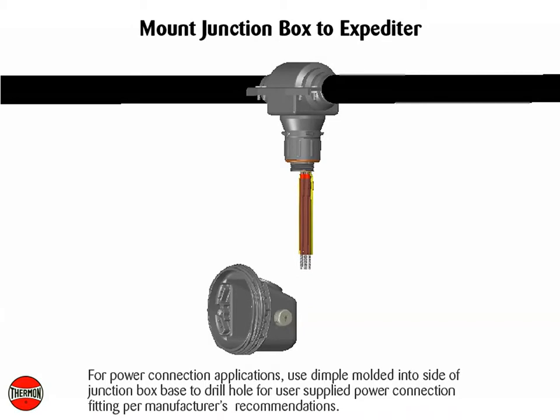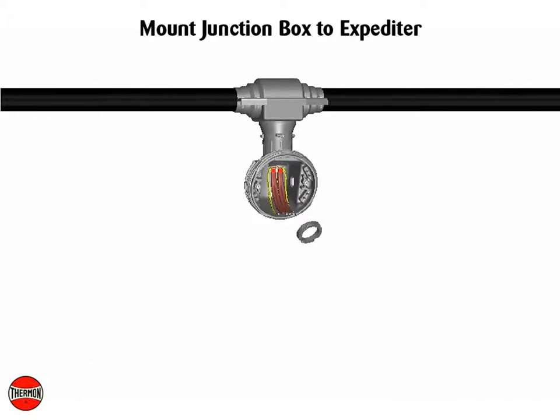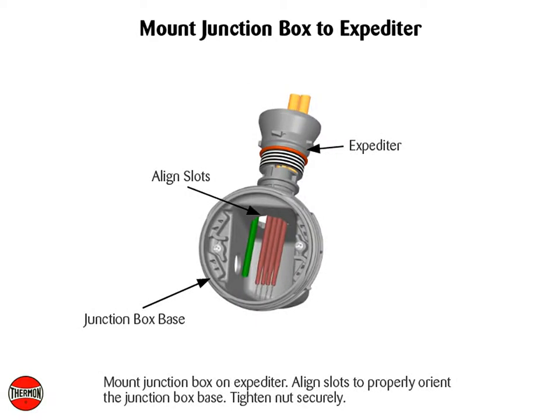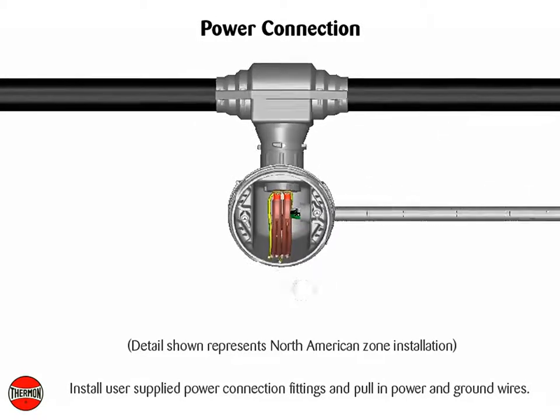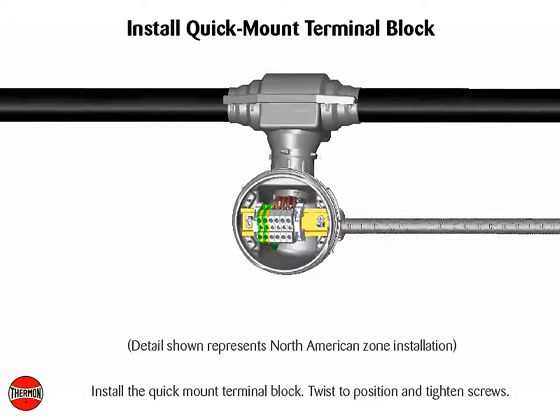For power connection applications, use the dimple molded into the side of the junction box base to drill a hole for the user-supplied power connection fitting, per manufacturer's recommendations. Mount junction box on expediter. Align slots to properly orient the junction box base and tighten nuts securely. Install user-supplied power connection fittings, and pull in power and ground wires. Install the quick mount terminal block, twist to position and tighten screws. Complete system wiring between fabricated heat trace and power supply wiring.